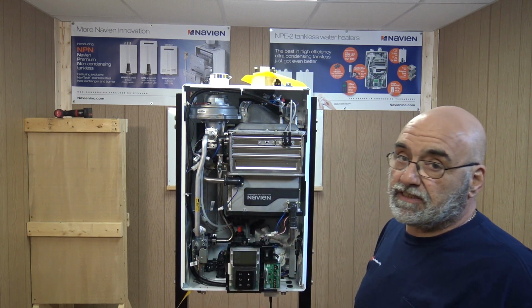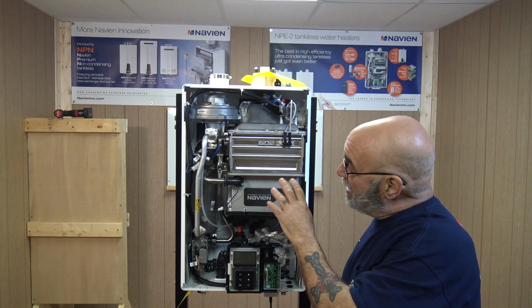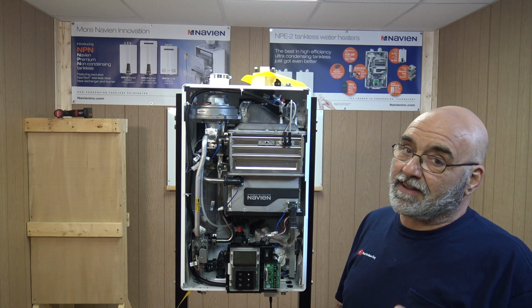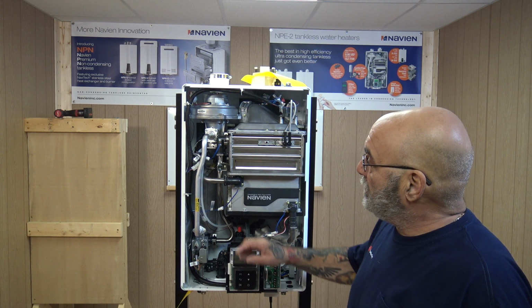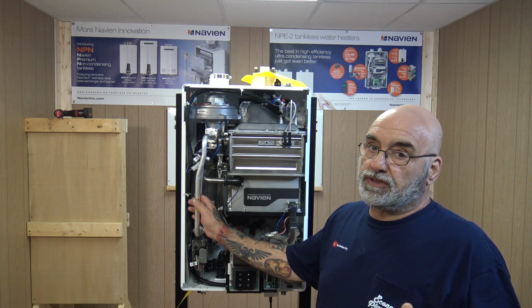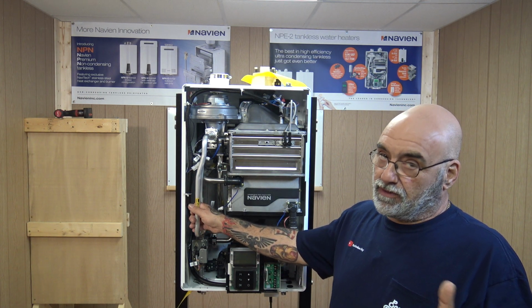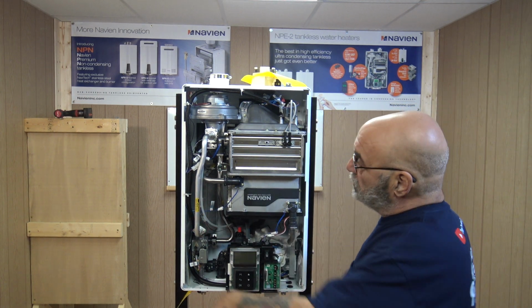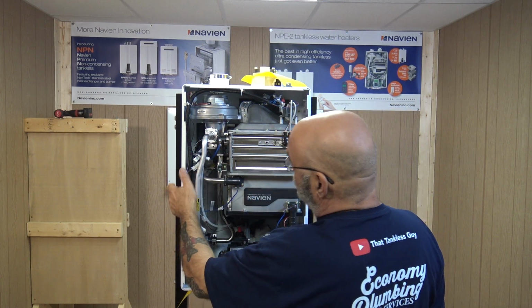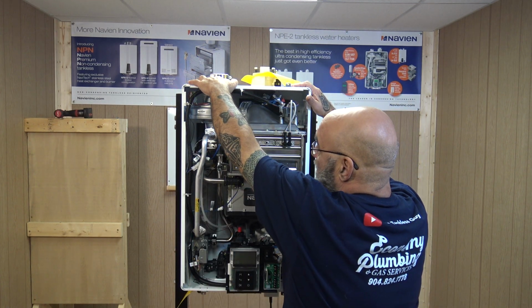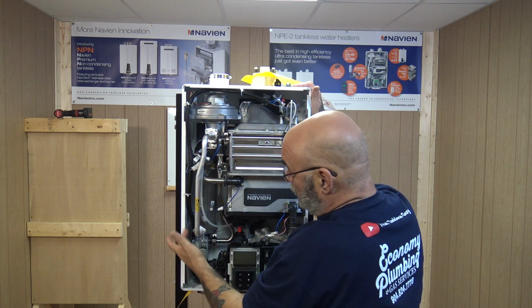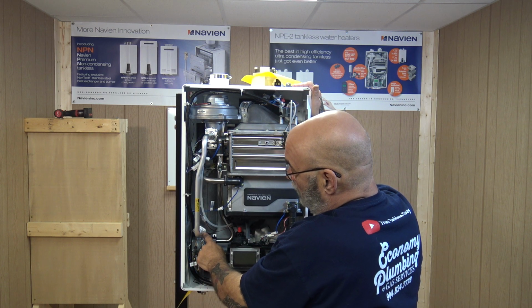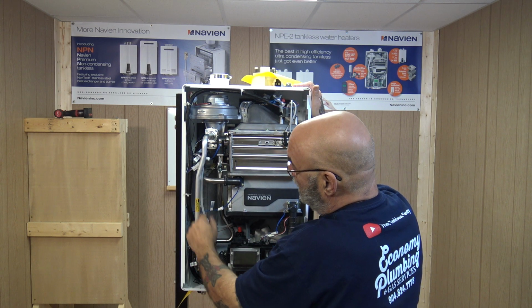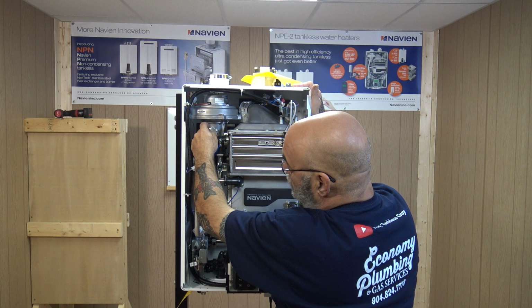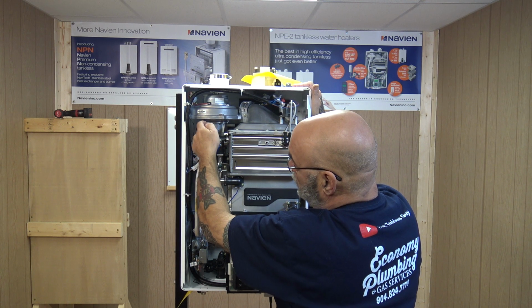It's the metal onto the aluminum, kind of like seizes it in a little bit. But I've only had to use the actual pliers twice. So you're removing 4 screws, 2 screws, take it down. I always put it up here. You don't want to get the face of these dirty. Make sure the O-ring stays down here. Then you remove the 2 tiny screws, take out your orifice, put the new orifice in.